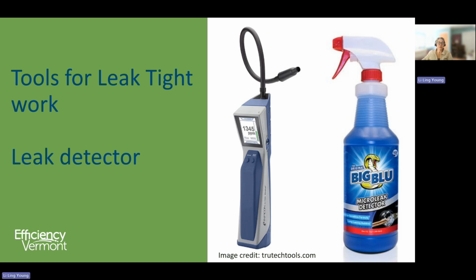Make sure you're familiar with how to use your electronic leak detector. Does it need calibration? What gases will give a false positive? What refrigerants does it detect? How often do the sensors need to be replaced? Does it require periodic cleaning? And what's going to damage its accuracy?